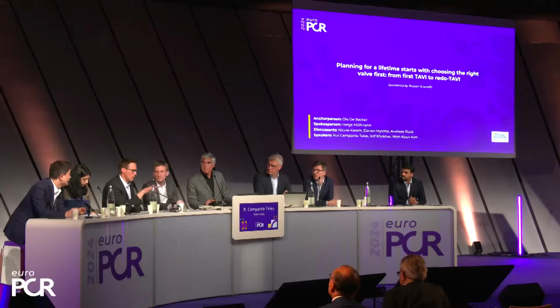Can I say one more thing? The reason that the pacemaker rate is so low is that when you look at Evolut and you look at Navitor, it's the very bottom of the frame. That's where the radial force is. That's what's pushing out. It's not the case with this valve. The radial force is 5 to 7 up. That's why if you implant this valve high, you don't get any benefit. You lose because you get more PVL, you have less radial force, and it pops up. So you implant this thing at 5 to 7, but know that what's underneath in the ventricle, in the LVOT, is much softer than what you get if you implant an Evolut or a Navitor, for example, at 5 to 7.